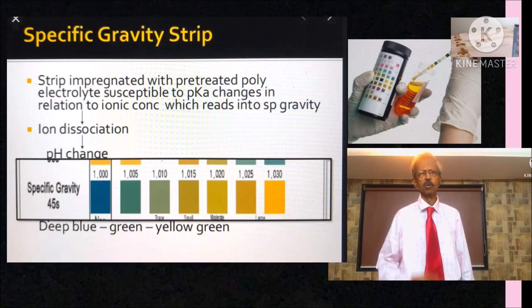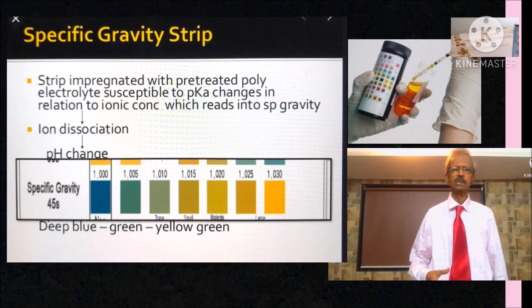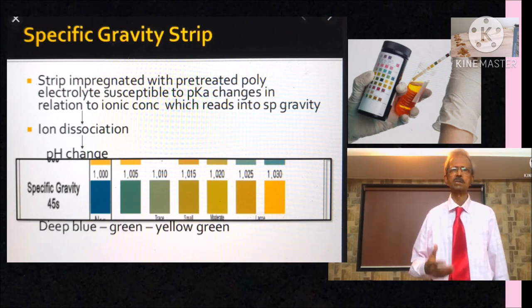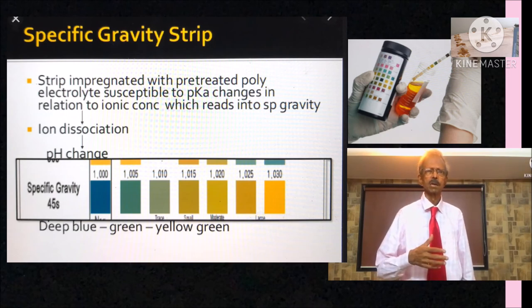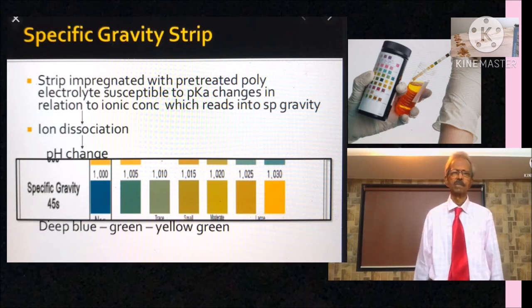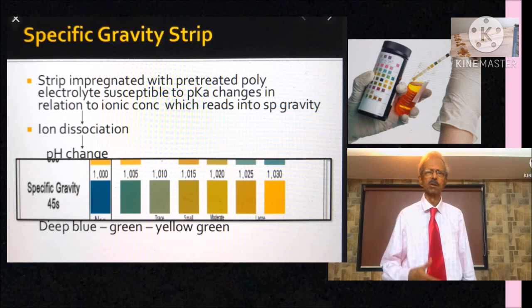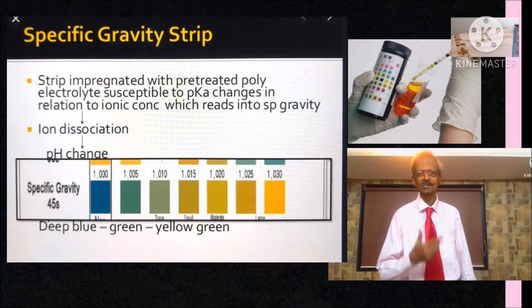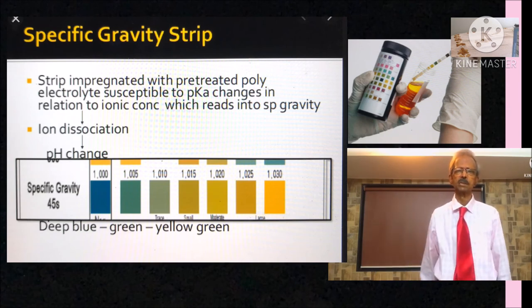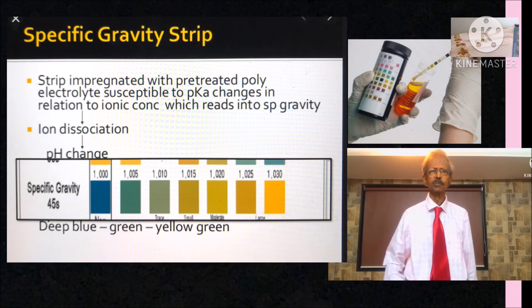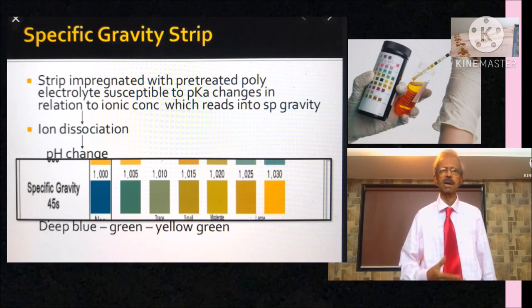For specific gravity, the reaction area contains pre-treated poly electrolytes and bromothymol blue. When the strip is dipped in urine, depending upon the concentration of ions in the urine which indicate a higher specific gravity, the poly electrolytes dissociate. And then the bromothymol blue changes the color. Higher the specific gravity of the urine specimen, more acidic is the reagent area. And the color of the reagent area ranges from deep blue-green to yellow-orange for higher ionic concentrations.